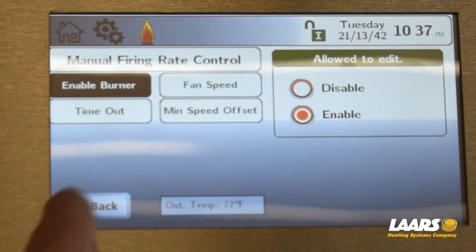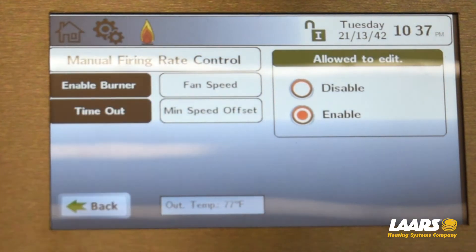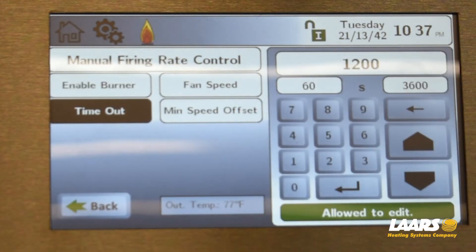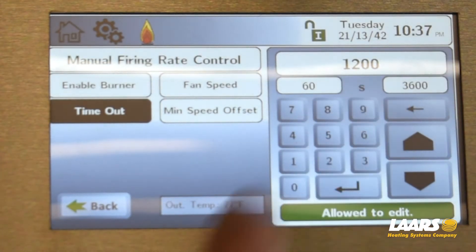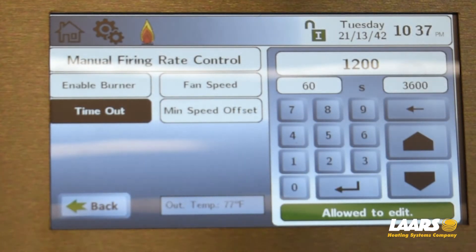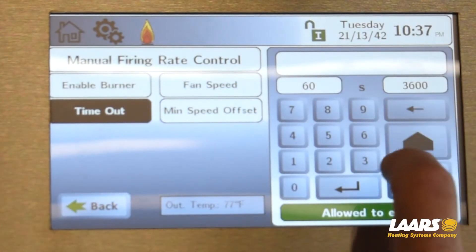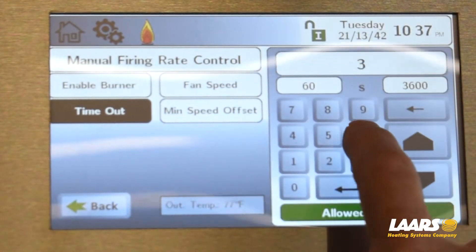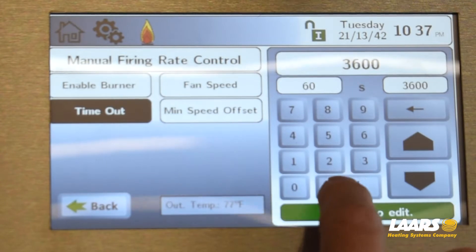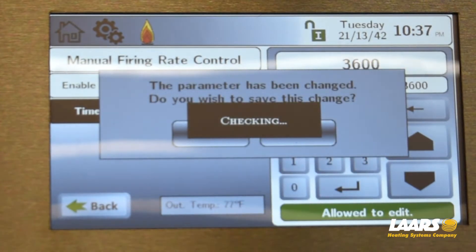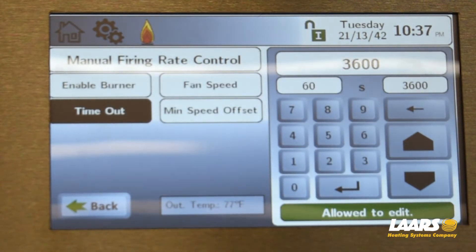Just below that is timeout — that's how long you'll be able to stay in combustion setup, and it's in seconds. The default is about 20 minutes. Back that out and type in the maximum of 3600, which will give you an hour to complete combustion setup.